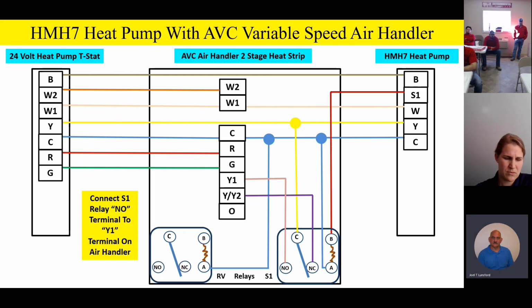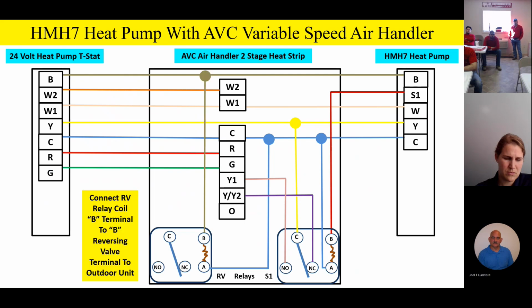Now on the RV relay, that second relay, we're going to take the other side of the coil and tie it onto the B terminal. The reason is we're going to switch this relay. I want you guys to think about it. We'll show you the animations here in a little bit. We're going to be switching the RV relay anytime we have a heating call from the thermostat, calling for B terminal. We're going to tie it onto that reversing valve terminal. So anytime we're calling for heating on the outdoor unit, we're going to energize that RV relay.